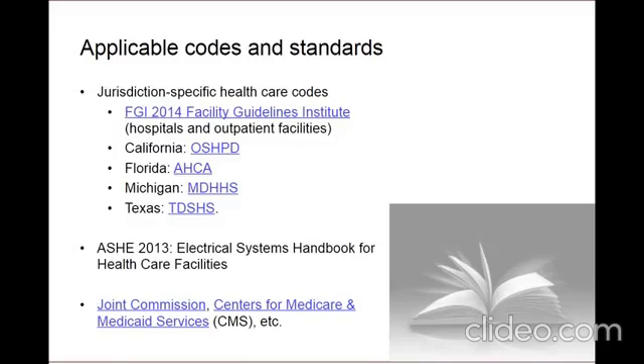And then there are a few other standards out there that weren't mentioned, such as the ASHE handbook. This one includes numerous diagrams on distribution systems and tips for electrical safety, power quality, and maintenance testing. This handbook mainly is just a handbook to be referenced by the designer for a more reliable system. I have not run into a jurisdiction yet that views this as code. Just be aware that it's out there.